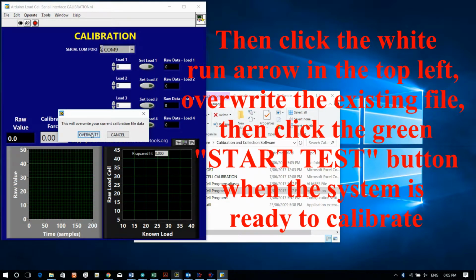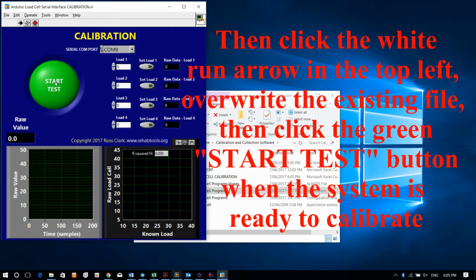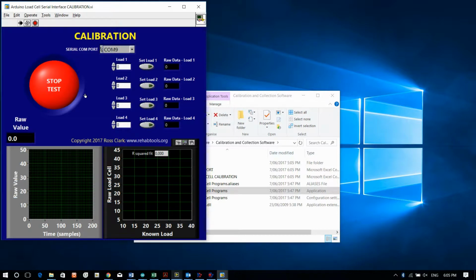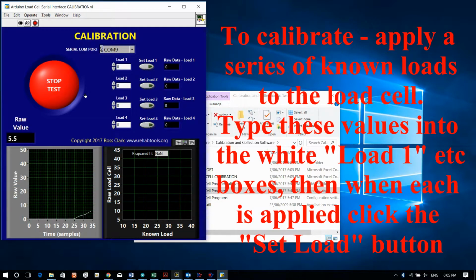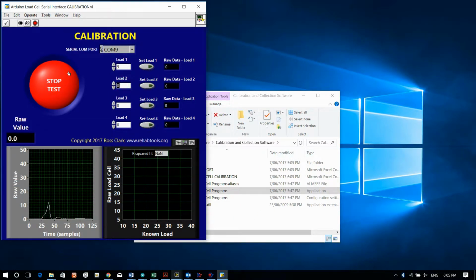We're going to overwrite the existing calibration file data and allow us to create some new ones. Now when it's green start test, you can click it and it'll take a few seconds, and now we have the load cell going. That's just me putting some weight on the load cell to make sure it's working, playing around with it a little bit. And now I know the loads I'm going to do. It's 5 kilos, 10 kilos, 15 kilos, and 20 kilos. They're the 4 loads I'm using for calibrations.